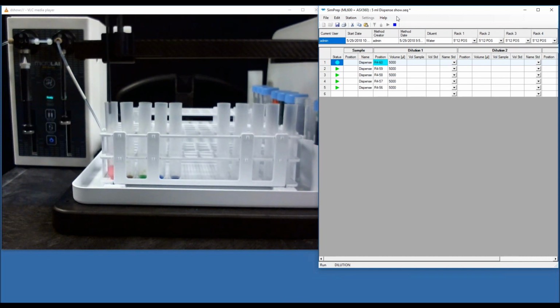Now you should see it in the first tube. There it's dispensing. And because this is just a dispense protocol, it doesn't have any sort of a rinse program, so it'll go directly from one tube to the next. Hopefully you can see the big syringe is the only one moving. As it's not pulling up any sample aliquot, everything is directly controlled by the large syringe to facilitate the speed. And the software is designed so that it will automatically select, from the syringes installed, the best syringe to give you the best accuracy for any movement that you program it to do.